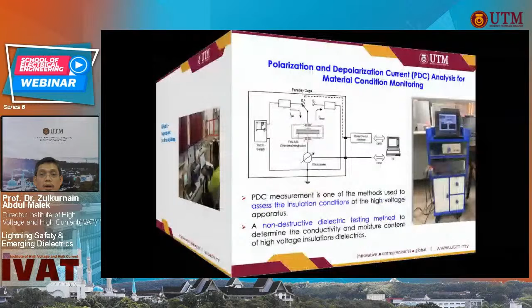Basically, you have an insulation here, whereby we can charge it using a voltage, and then because of the dielectric, it starts to polarize, and therefore a certain current will flow. And we measure this current, and after a certain time, we disconnect the voltage, and it depolarizes again, and we measure this current. And the response can indicate the condition of the dielectric. For example, in a transformer, you can see here the polarization current. If it behaves in a certain way, for example here, it may indicate aging of the oil, and here, content of water inside the oil.